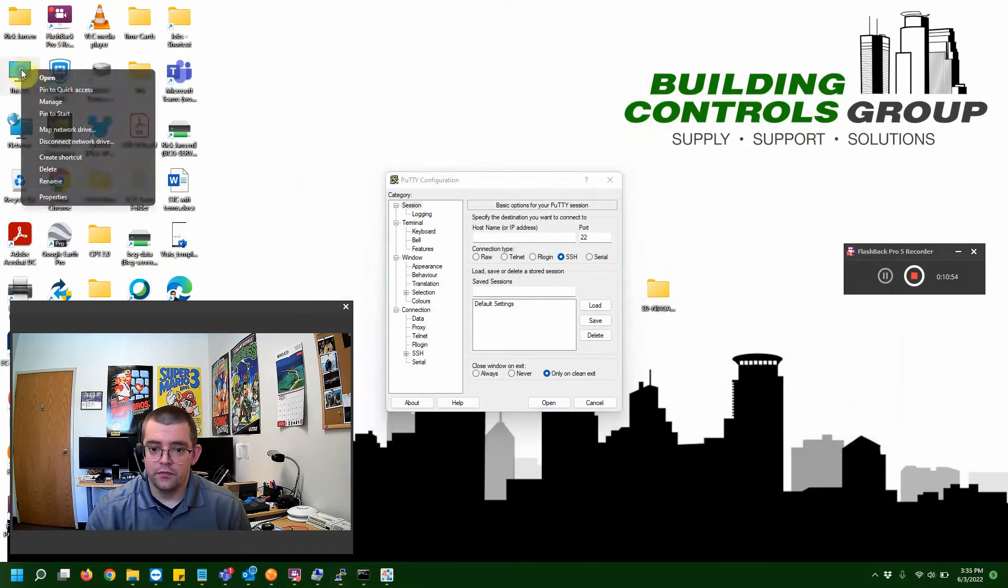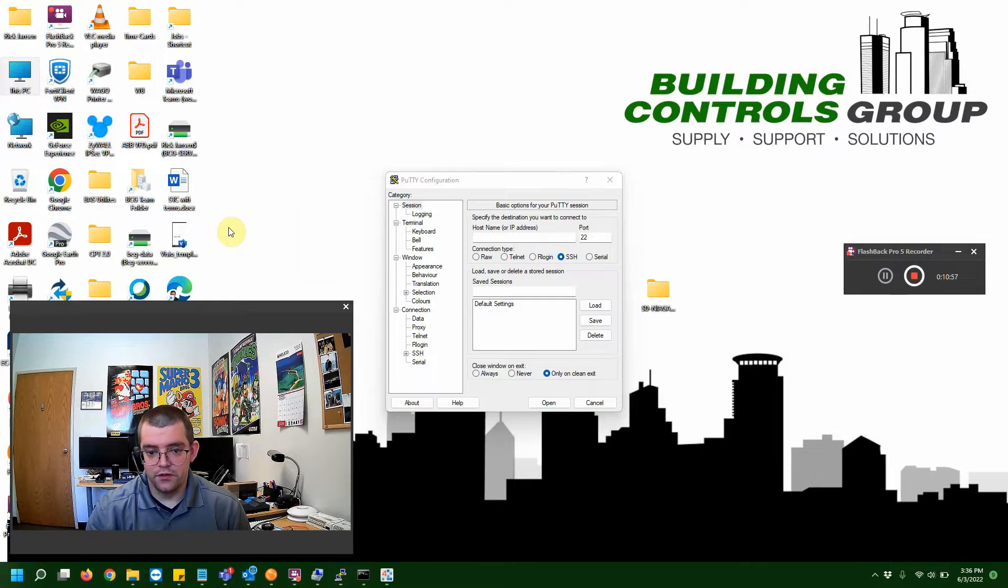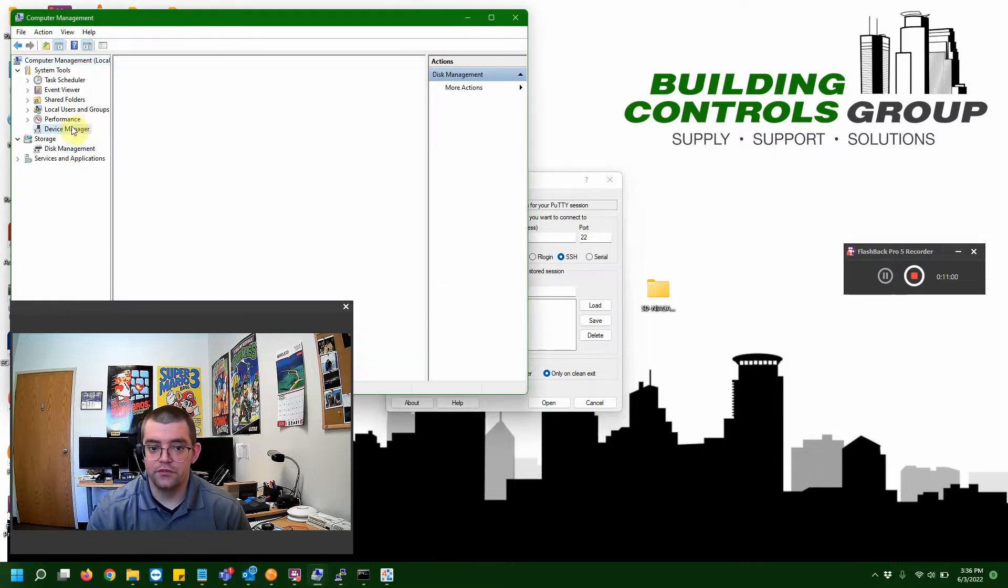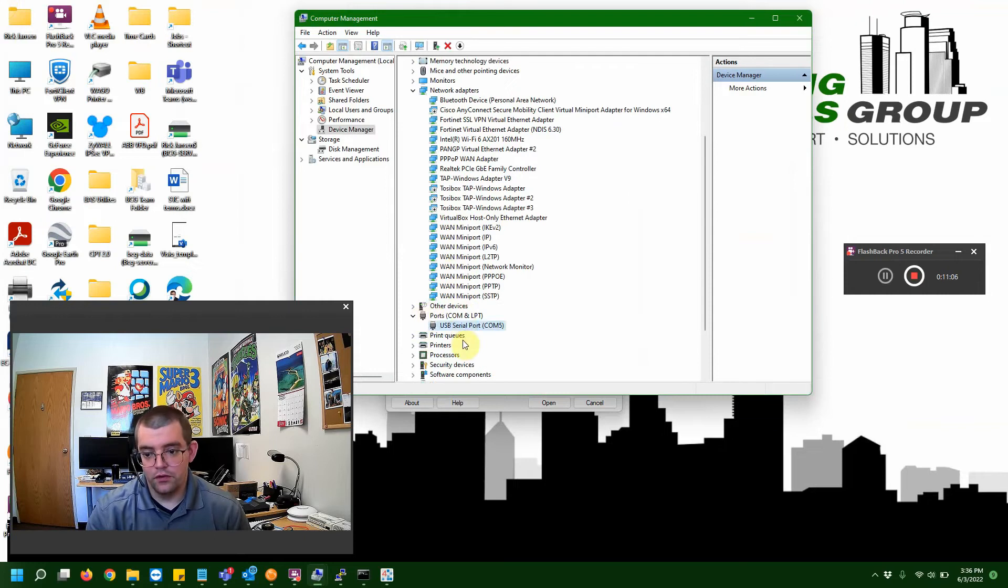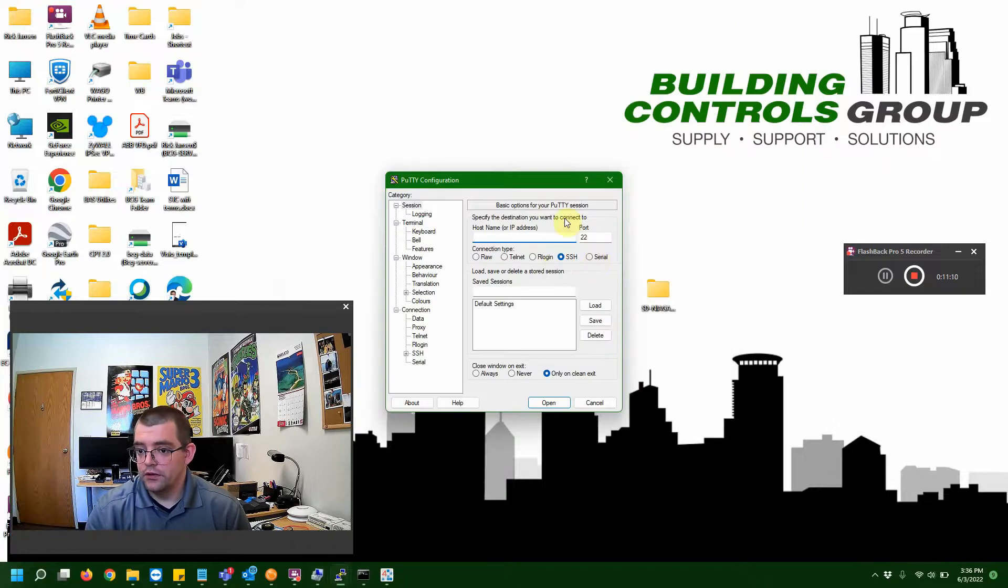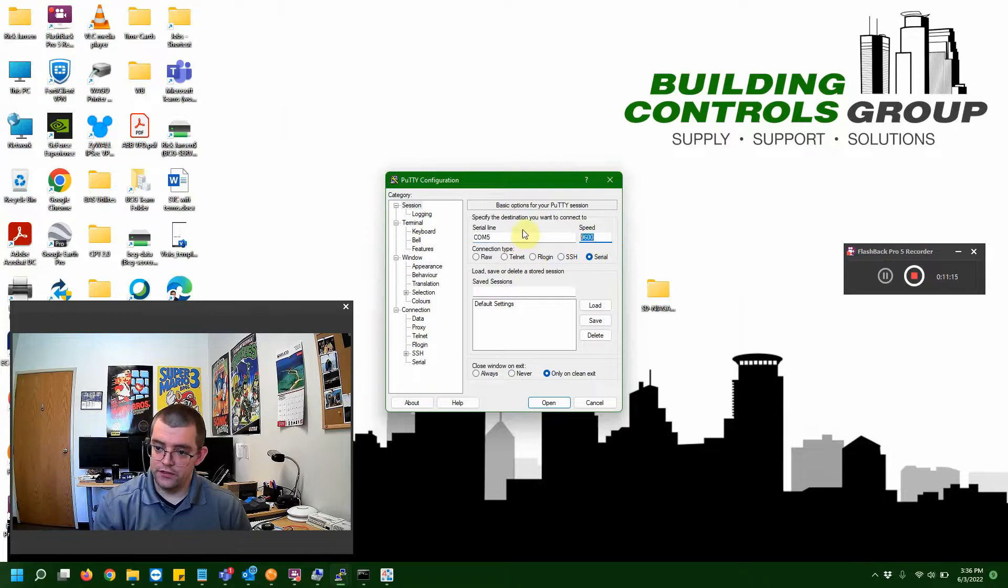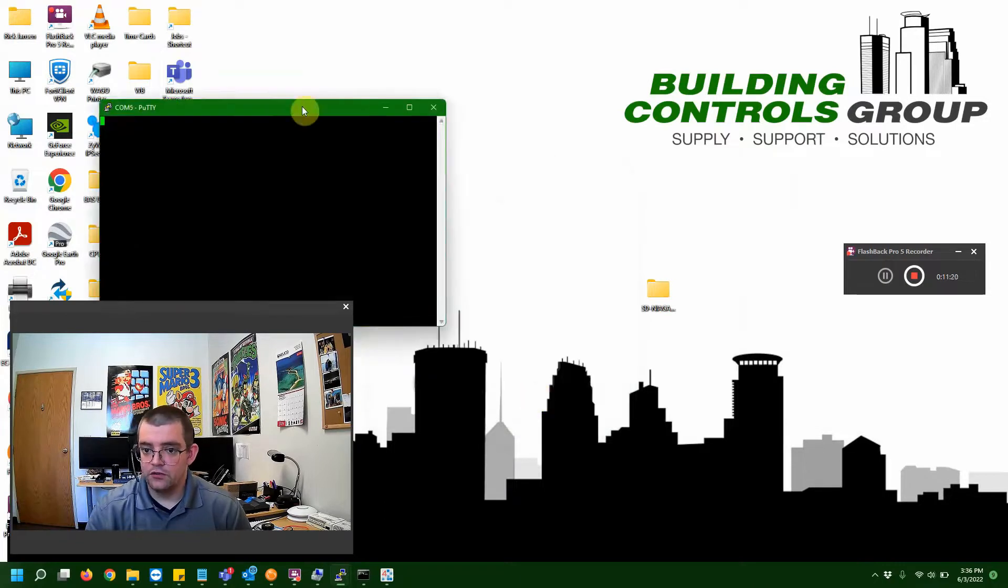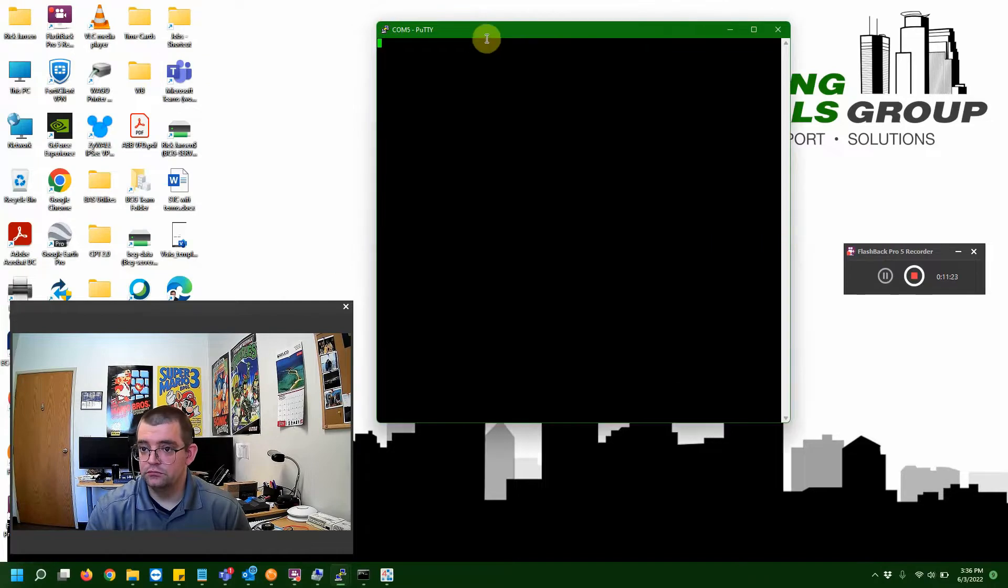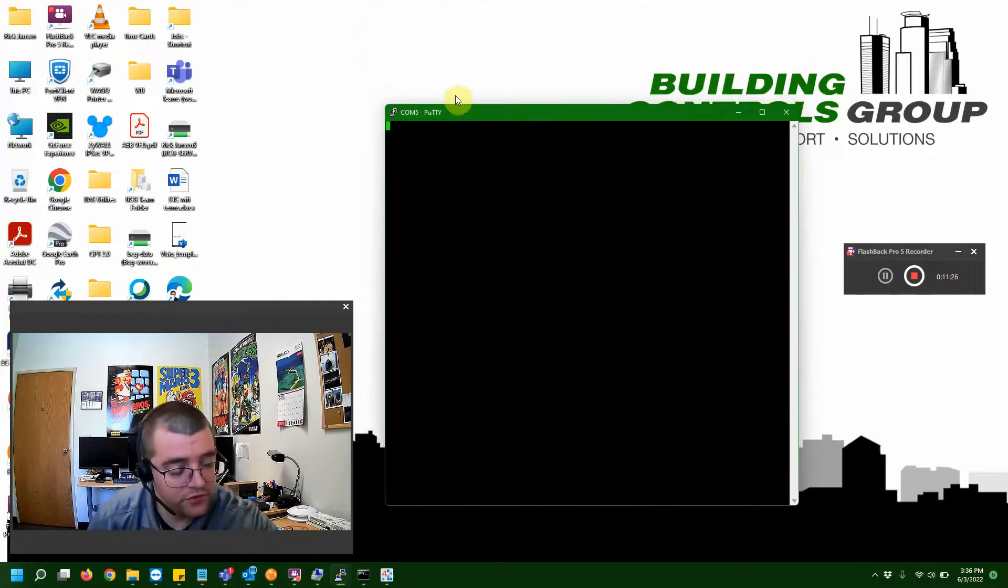If you remember last time, we went to find our COM port through the device manager. Let's go ahead and open that up. And, we can see that my Jace is on COM5. So, we're good there. Serial, COM5, and our baud rate is always 115,200. All right. So, we got our session started here. And, I'm going to go ahead and power up the Jace.